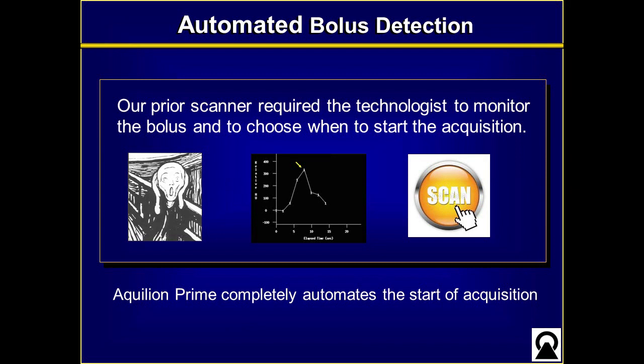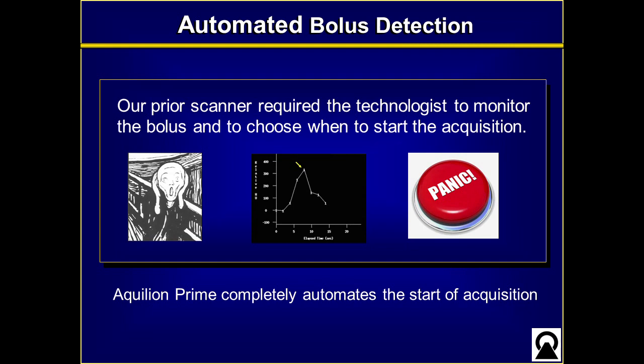Our prior scanner required the technologist to monitor the bolus and choose when to start the acquisition. The technologist needed to monitor the signal over time and make a split-second decision when the signal peaked, then hit the scan button — which frequently looked a lot like a panic button because they needed to get it right away to get the timing just right. As a result, on our old scanner we hardly ever used automated bolus detection.